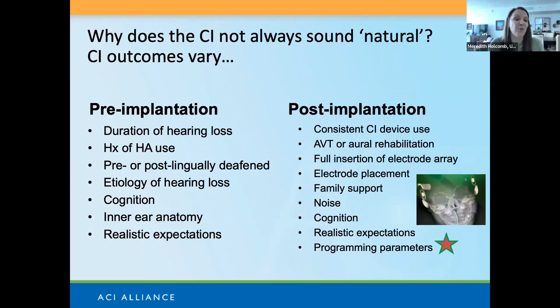And then post-implantation, there's a lot of things that we can control for, like fully inserting the electrode array, making sure the electrode is placed in the right place, consistent device use, which I'll mention again later. But other things that sometimes we can't control are how much noise you're going to be in when you're using the device, what your cognition level is, how that's going to play into your speech understanding. Something we can try to control, though, is your programming parameters. But there's a big caveat to this. Programming the cochlear implant is not always the answer. We have so many tools as audiologists to try to help you hear best with your implant. But we also have a lot of restrictions based on the anatomy, and we can't necessarily overcome what the brain is going to do with that sound.